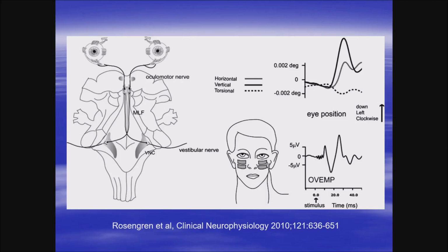So the setup again is simple. This is from the publication of Sally Rosengren, who initiated the discovery of this potential from the inferior oblique muscle. The setup again is simple, placing an active electrode on the orbital ridge in the middle. We will show this in the workshop later on. The reference electrode is below that, and the ground again, either on the forehead or on the sternum.